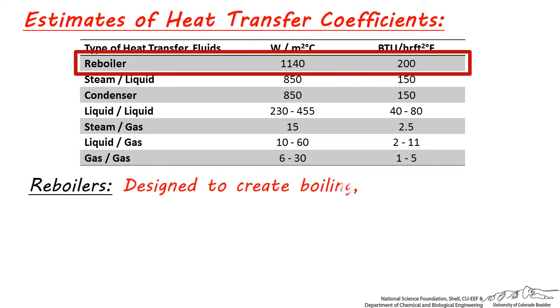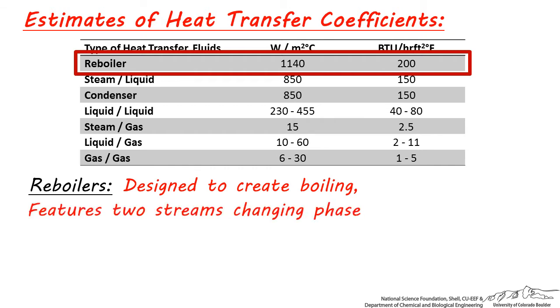Reboilers are heat exchangers which create boiling and have a high heat transfer coefficient because of their physical design and because they usually involve both streams in the heat exchanger changing phase. So the hot stream will condense into a liquid and the cold stream will be brought to a boil.